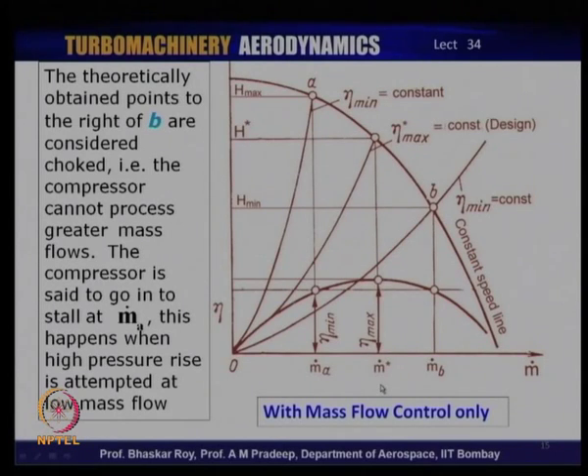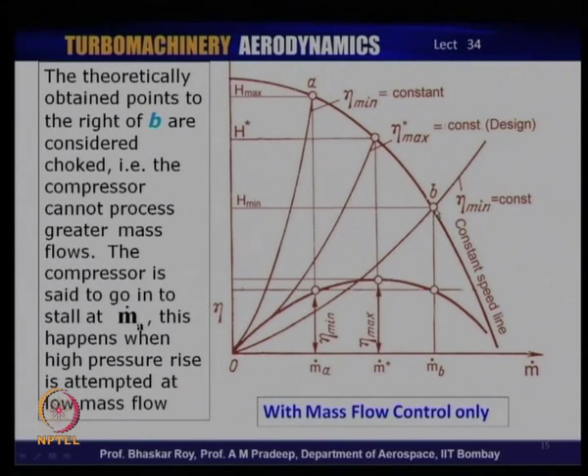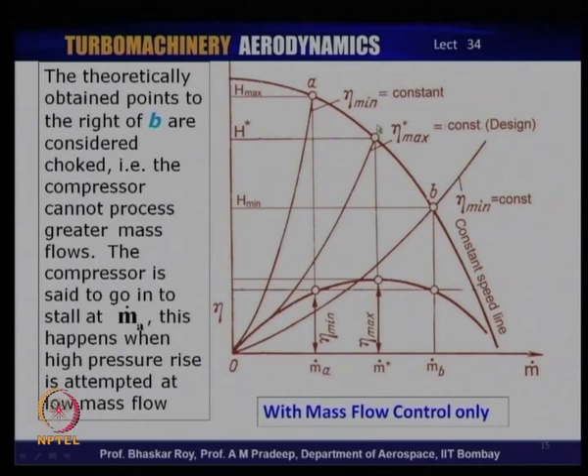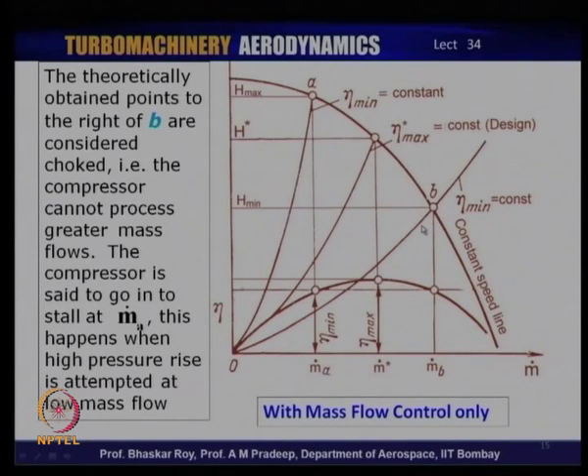With only a mass flow throttle control, the operation is along a speed line between point B — where the machine is choked at maximum mass flow — and point A — where minimum mass flow could lead to stall. Between A and B somewhere there is the maximum efficiency line, where you have the best efficiency of operation. Going away from that point, efficiency goes down: toward stall near A, and toward choking near B where efficiency is also somewhat lower. The maximum efficiency line decides the compressor operation in a natural manner.